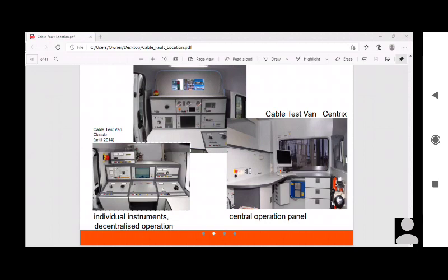Even if the cables are in a bunch, you will be able to identify it, because the receiver would continue to give you the leakage current also. So if there are adjoining cables which would have some effect on the signal generated through the signal generator and sent into the cable, you will still be able to identify the particular cable.